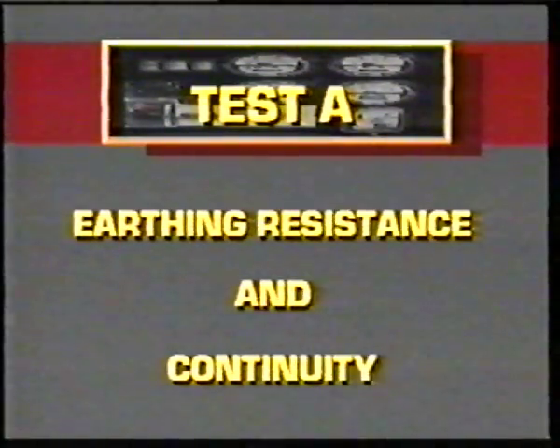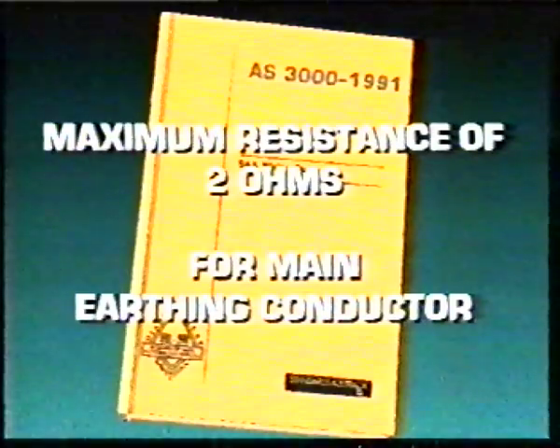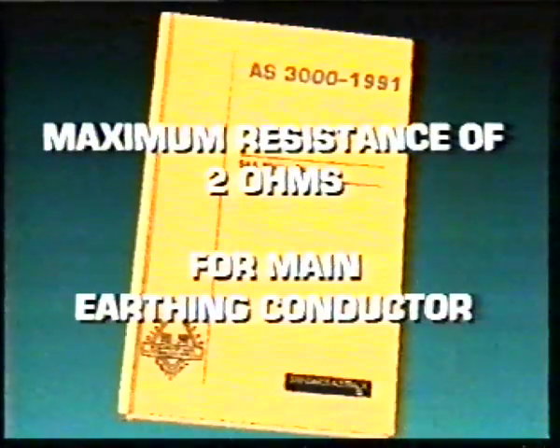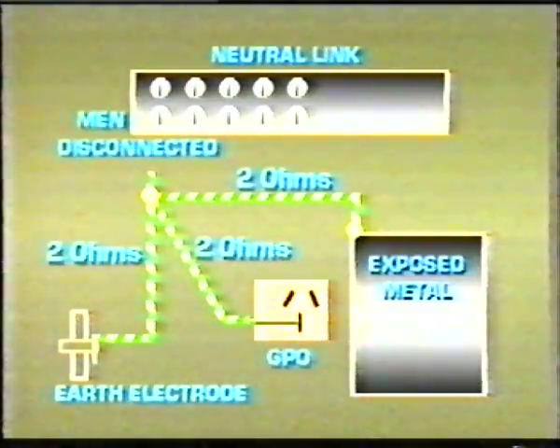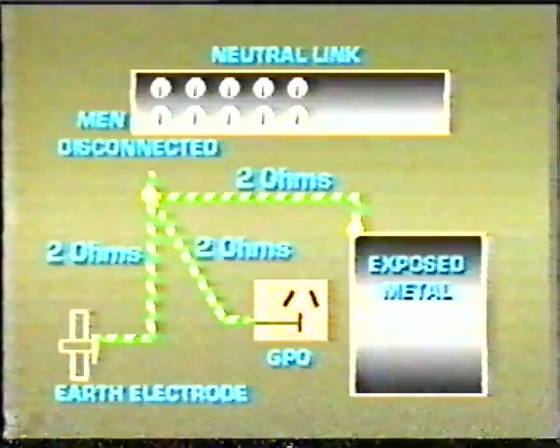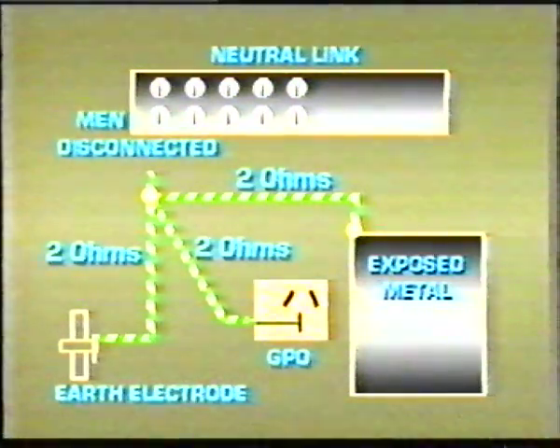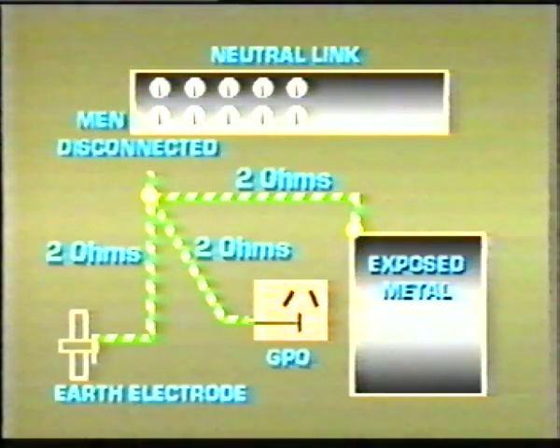Why is this test necessary? Because the earthing system must be installed in a manner that will cause circuit protection devices to operate if there's a fault between live parts other than the neutral and the general mass of earth. An effective earthing system will also ensure that equipment parts which are earthed do not reach dangerous voltages during such faults. What requirements apply? AS3000 generally requires a maximum resistance of 2 ohms for the main earthing conductor. That is, the conductor between the MEN connection and the earth electrode, and also between any point in the installation required to be earthed. For example, points defined as exposed metal, and earth terminals at socket outlets and the MEN connection. In some situations, this resistance must be reduced to ensure that the fault current will operate the circuit protective device.